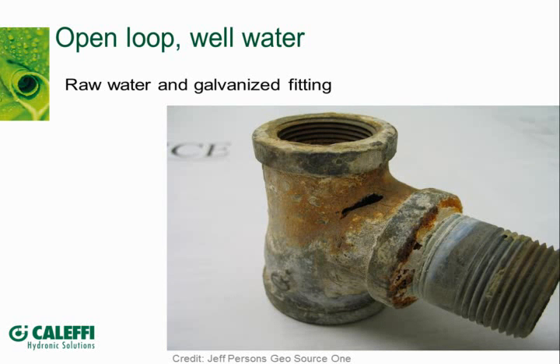The dielectric unions that are used at the top of hot water tanks are primarily steel, connected to copper piping, and they become a bit of the sacrificial anode in the system once the anode rod in the tank disappears. Usually those dielectric couplings become pretty well plugged up from corrosion or eventually perforate. Well, and the same thing there, I would say, Jeff, is, depending on where they were manufactured, the quality of the zinc coating that's put on there, once that goes away, if they're not plated well, or if they're not plated with a good quality, then you're right, you just have a steel fitting on there. Yeah, once it goes, it's gone. You're right. And it's a rapid process. It doesn't take too long.